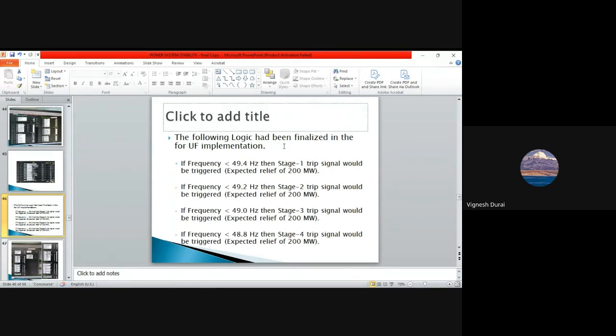If the frequency is reducing drastically and reaches 49.4 hertz, it will immediately trigger signal 1. The stage 1 trip would be triggered, expecting a relief of 200 megawatt. Immediately it will trip. If the frequency keeps reducing and reaches 49.2 hertz, then the stage 2 trip would be triggered. If the frequency is below 49, stage 3 will be triggered. At 48.8, stage 4 will be triggered. Everything will be triggered immediately. Every tripping has a load relief of 200 megawatt, so that the frequency goes back near 50 hertz.